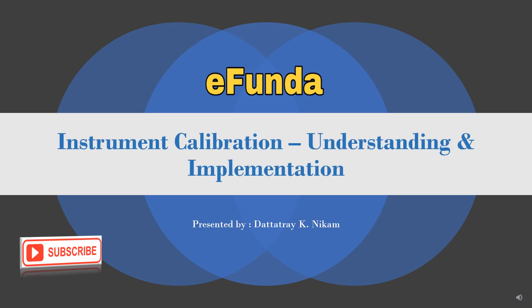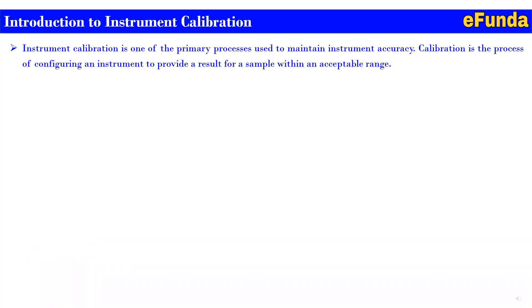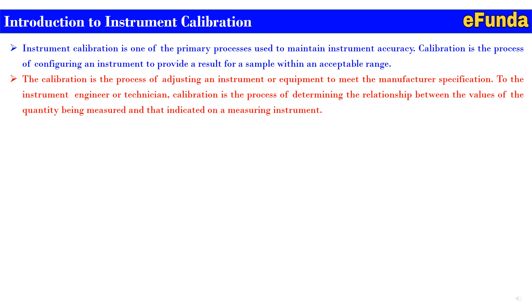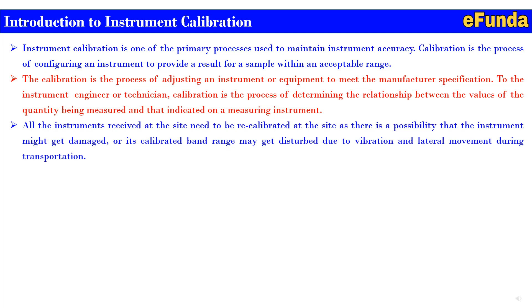Let's begin with our today's topic: instrument calibration — understanding and implementation. Instrument calibration is one of the primary processes used to maintain instrument accuracy. Calibration is the process of configuring an instrument to provide a result for a sample within an acceptable range. It is also the process of adjusting an instrument or equipment to meet the manufacturer's specification. To the instrument engineer or technician, calibration determines the relationship between values of the quantity being measured and those indicated on the measuring instrument. All instruments received at site need to be recalibrated, as they may get damaged or their calibration range disturbed due to vibration and lateral movement during transportation.